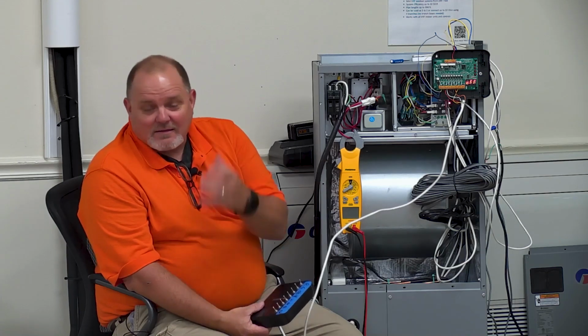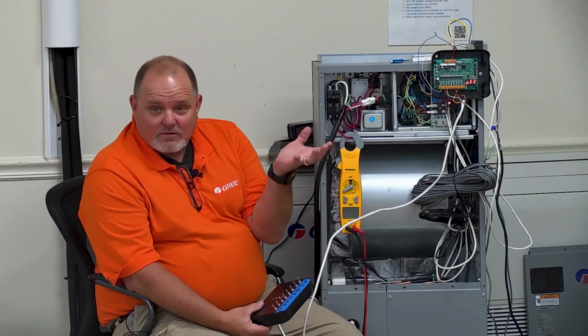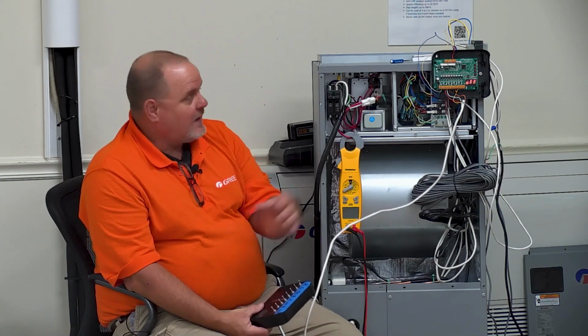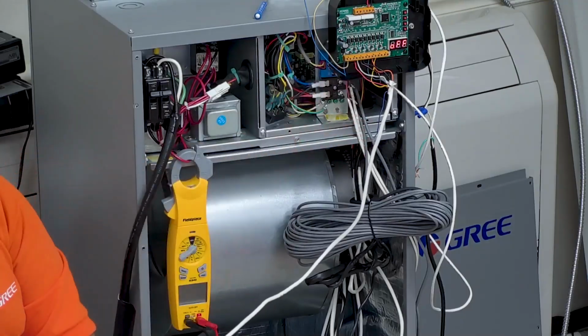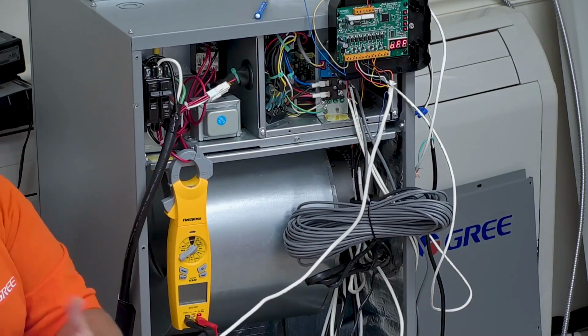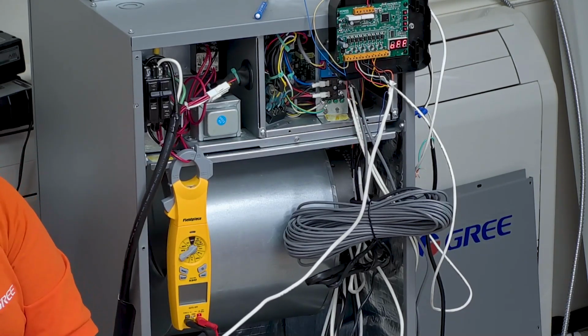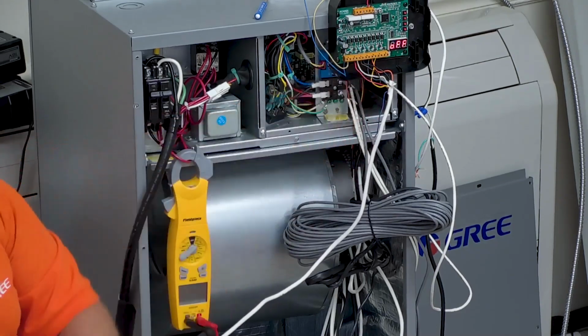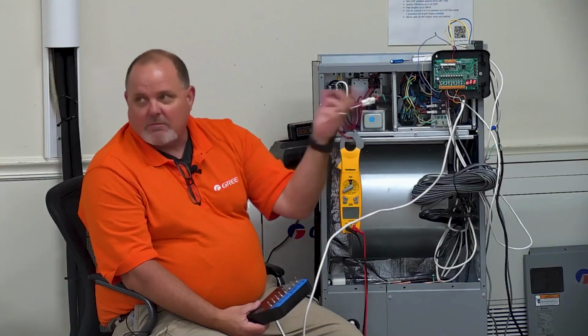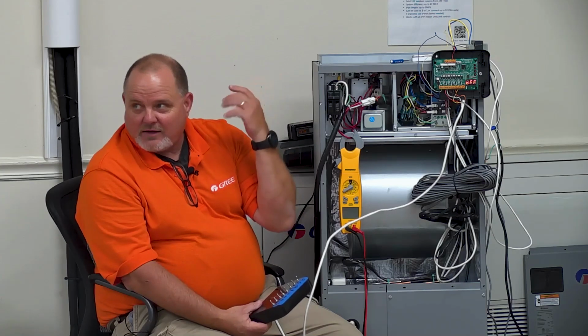Just don't forget about, you have to have a master. Because I actually did that on my own unit in my house. First time I hooked up the prototype, I'm like, why am I getting this error code? Well, dummy me didn't think about the fact that the wired controller I disconnected was the master, and then when I hooked this up, I didn't have it set up to become the master, and then I got the error code for no master indoor unit. So all I had to do was go back in, reset that P code, and it became the master, and the problem went away, and I was able to run the whole thing, and it all worked just fine.